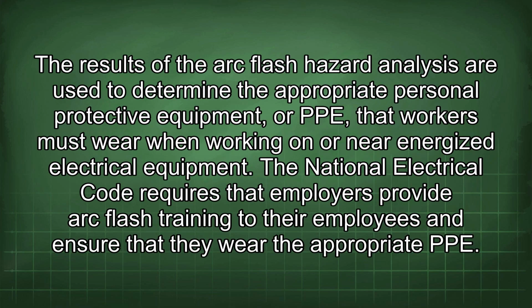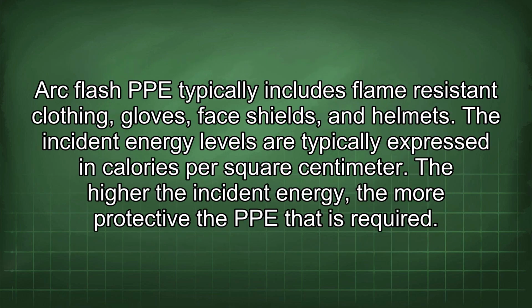The results of the arc flash hazard analysis are used to determine the appropriate personal protective equipment, or PPE, that workers must wear when working on or near energized electrical equipment. The National Electrical Code requires that employers provide arc flash training to their employees and ensure that they wear the appropriate PPE. Arc flash PPE typically includes flame-resistant clothing, gloves, face shields, and helmets. The incident energy levels are typically expressed in calories per square centimeter. The higher the incident energy, the more protective the PPE that is required.